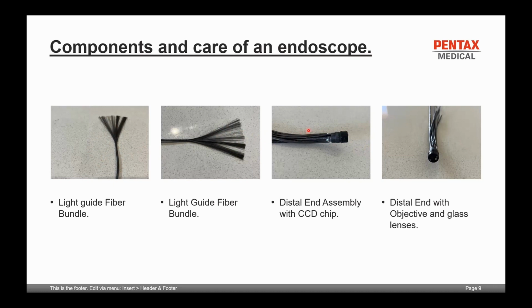All your stuffing is positioned inside the insertion tube of the endoscope and is coated with a powder, which is a molycoat or graphite powder. So you can imagine if any fluid contamination occurs to your endoscope, that molycoat powder is going to turn into a bit of a paste. It's going to harden, and these fragile light guide fiber bundles are then going to be compromised and potentially break the next time the endoscope is angulated. So at some stage, if your endoscope has fluid contamination with it, the fiber bundles do start to become brittle because of the graphite powder, and you'll start obviously seeing a deterioration of the light of the endoscope during the procedure.